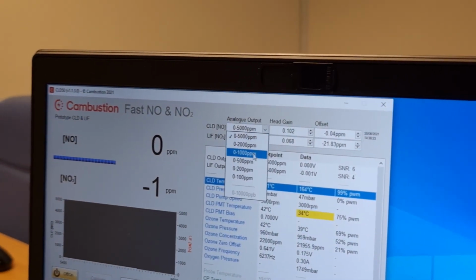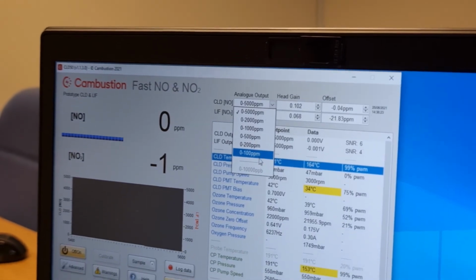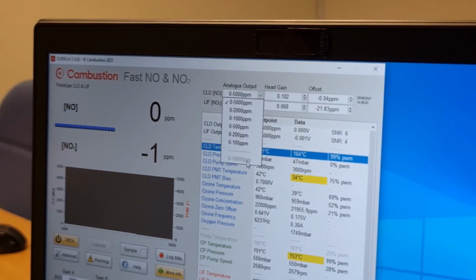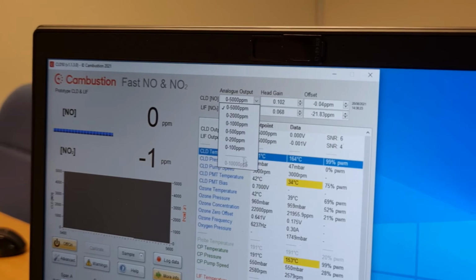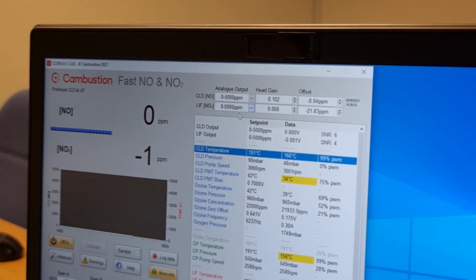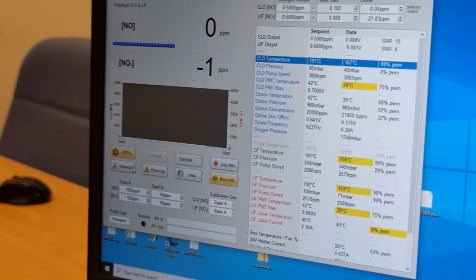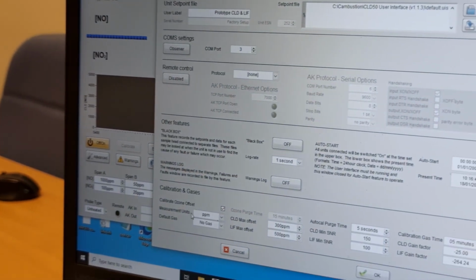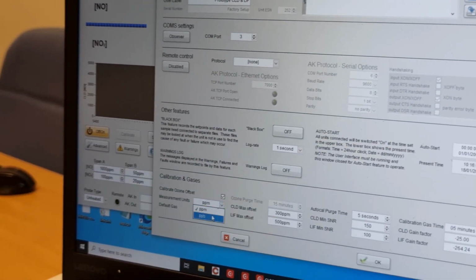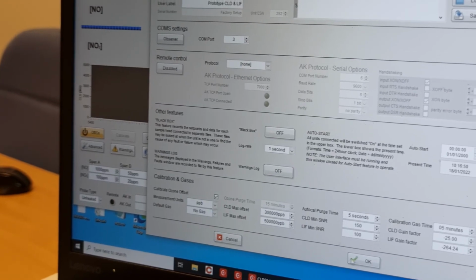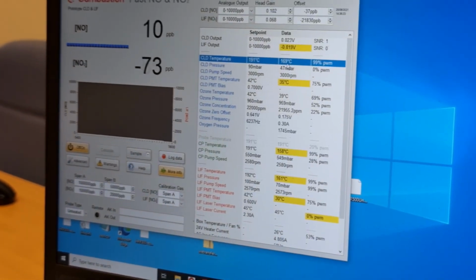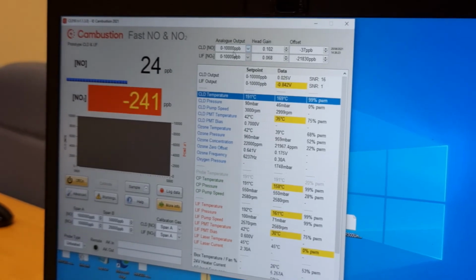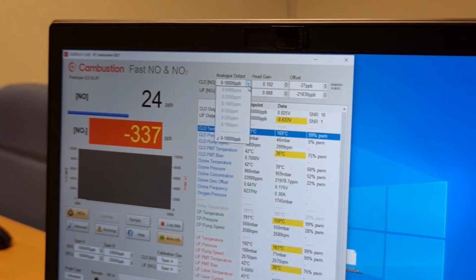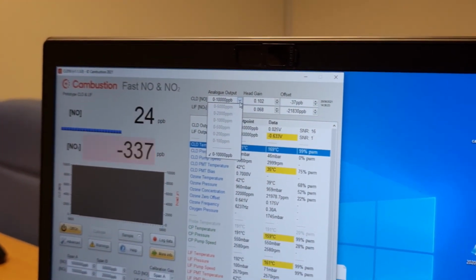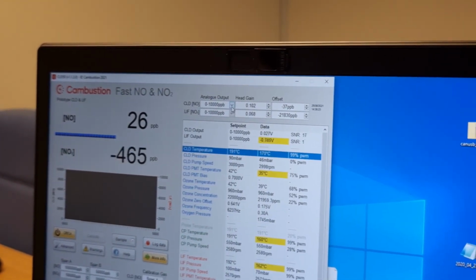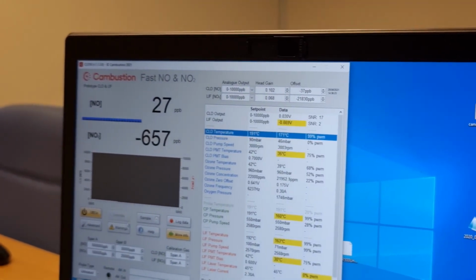But there are other ranges available, and if you're measuring in atmospheric conditions, you may want to measure in the parts per billion range, and to do that you open up the Advanced tab, and in the bottom here the measurement units can be changed from ppm to ppb, which will require some recalibration, but you can see that the outputs here are shown as parts per billion, with the ppm outputs grayed out. The other thing I should show you are the warnings.